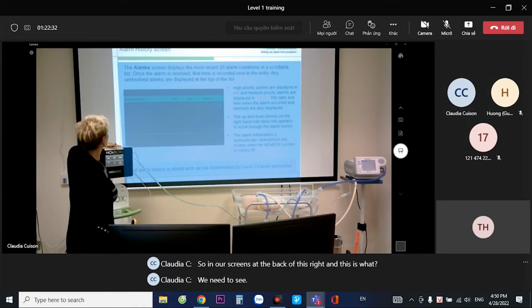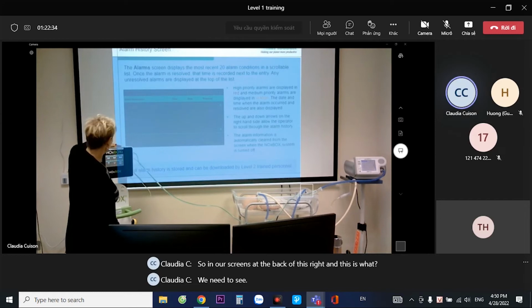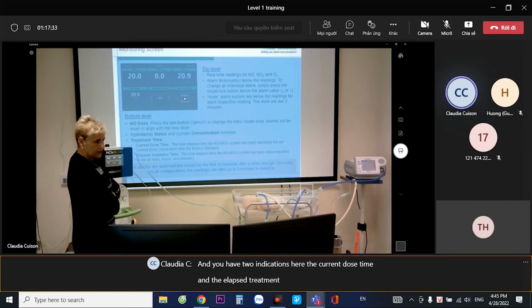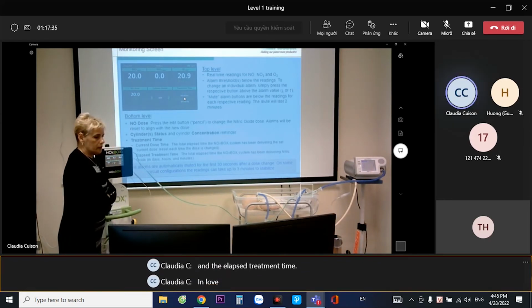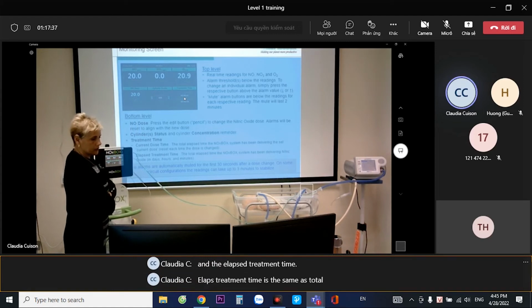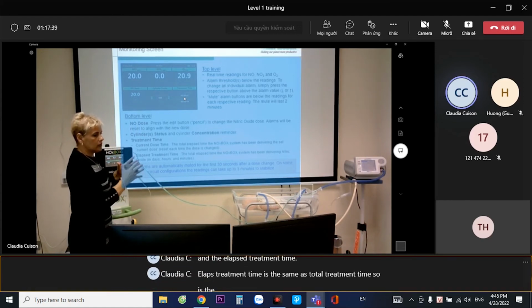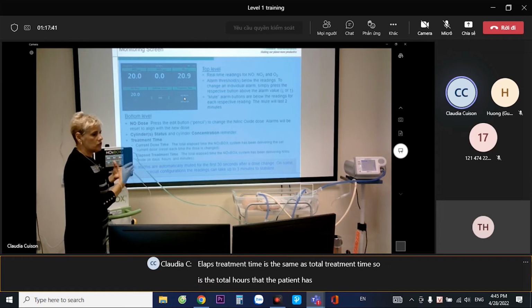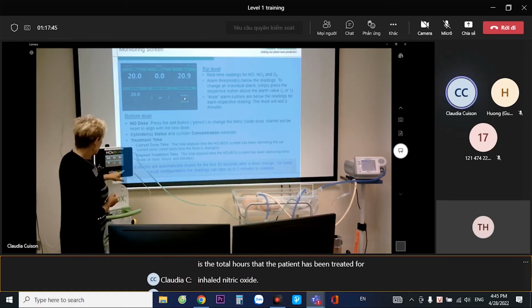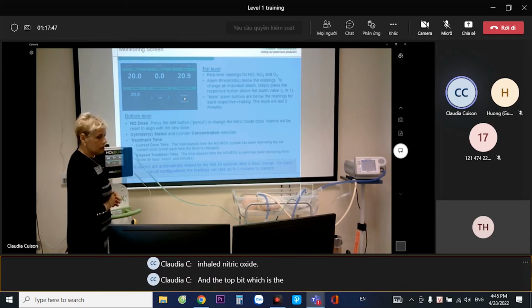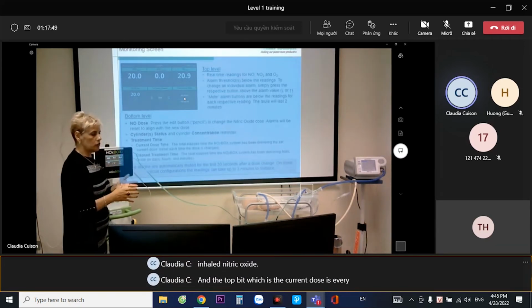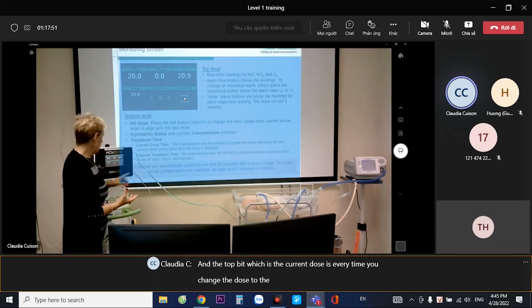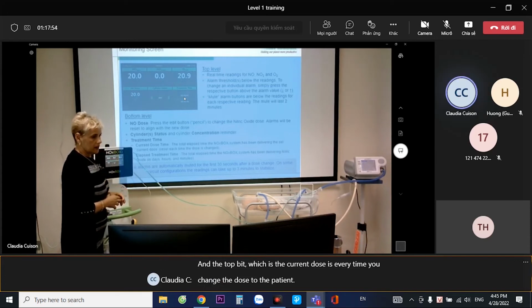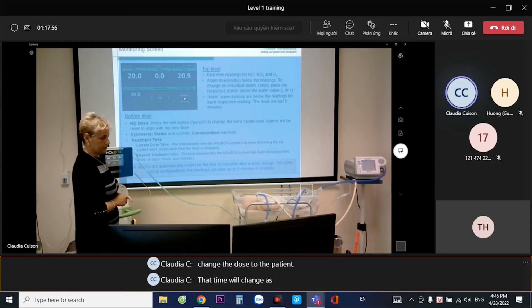And you have two indications here, the current dose time and the elapsed treatment time. Elapsed treatment time is the same as total treatment time, so it is the total hours that the patient has been treated for inhaled nitric oxide. And the top bit, which is the current dose, every time you change the dose to the patient, that time will change as well.